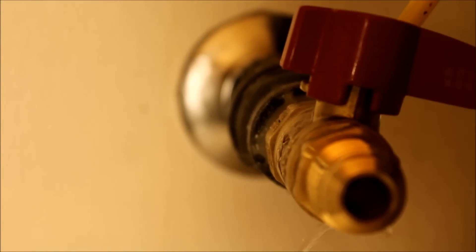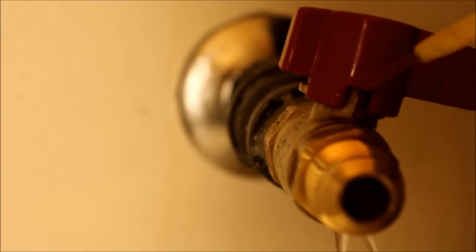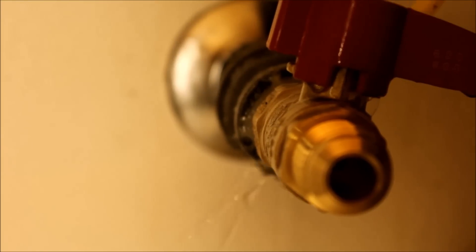I'll leak test on the inside now. Just spray all over this. I don't see any bubbles. Everything looks really good. I'm really flooding this thing. You don't have to do this much, but I'm being extra safe.